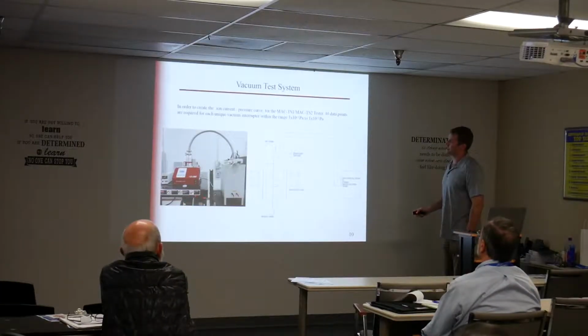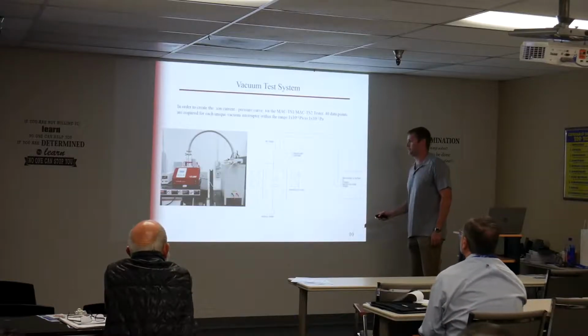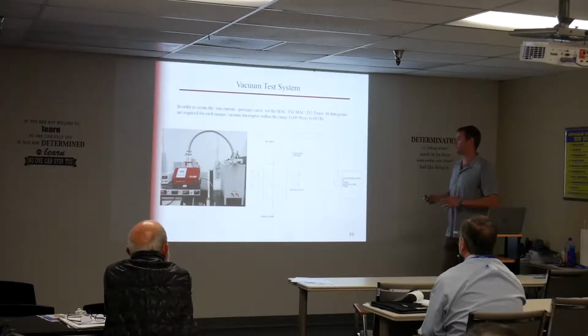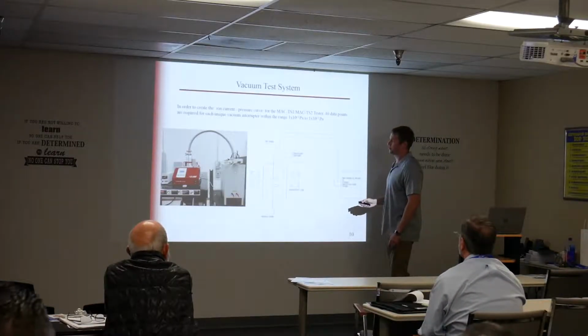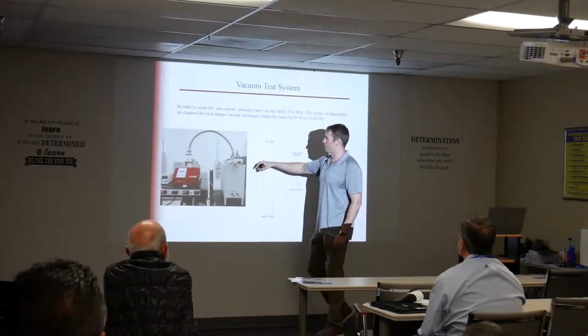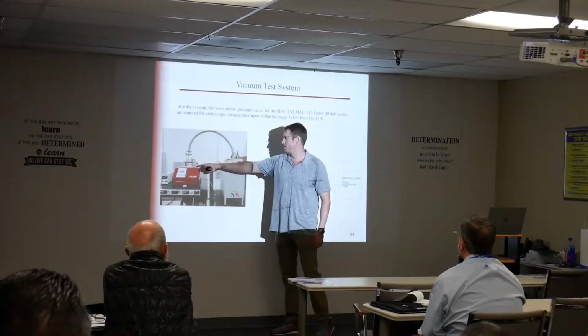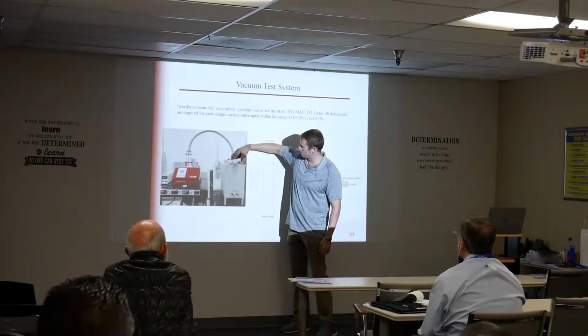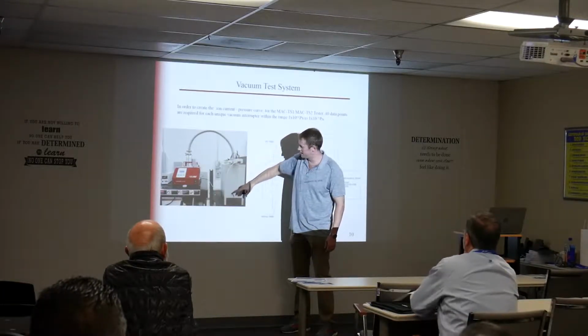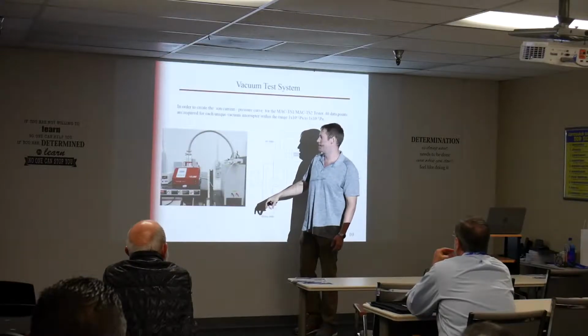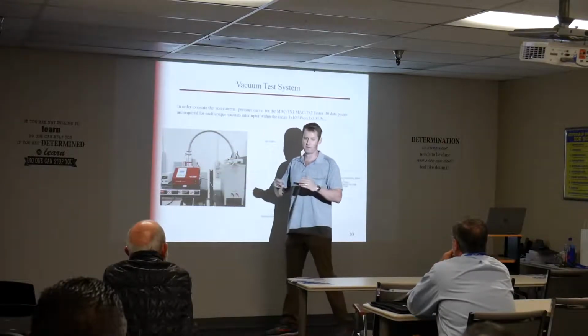So this is my test setup in the lab. My test set's measuring current, but it outputs pressure. So I've taken all the different size interrupters. I puncture them with a vacuum fitting, hook it up to a turbomolecular pump. This is our fixed coil, so there's a loose interrupter placed inside of here. This is hooked up to my lab test set. So with this turbomolecular pump, I'm controlling the pressure.